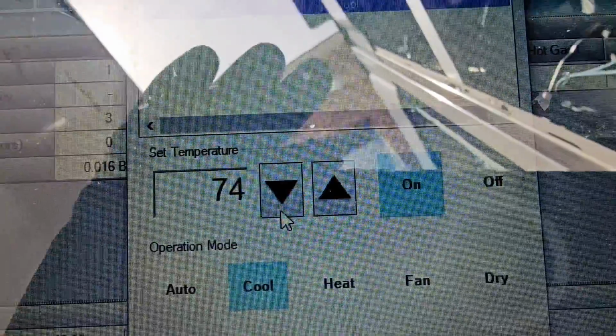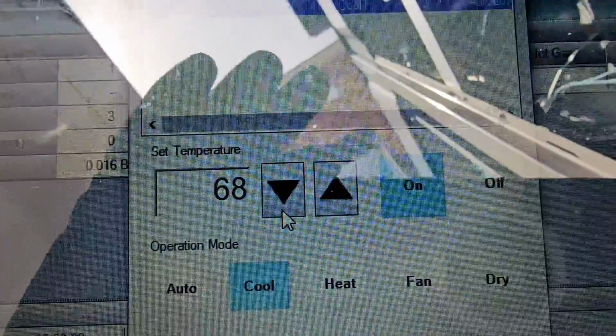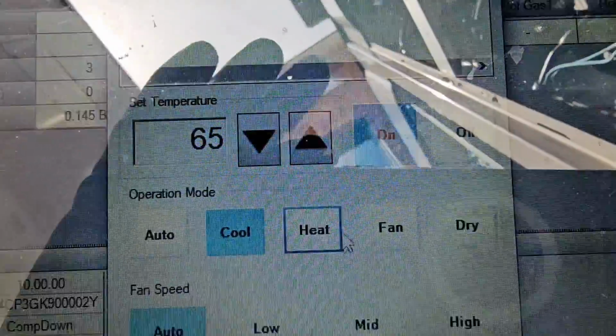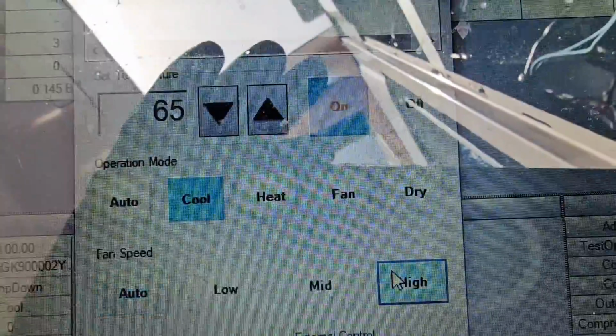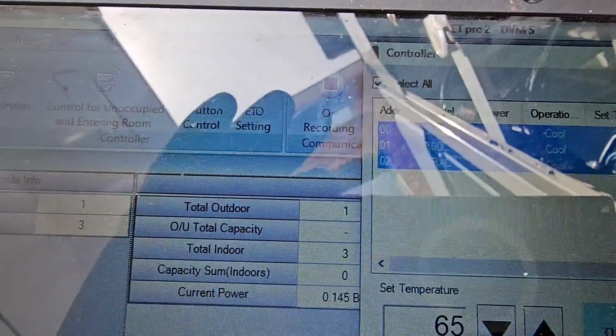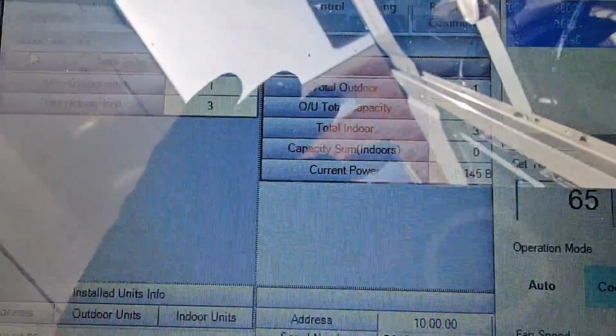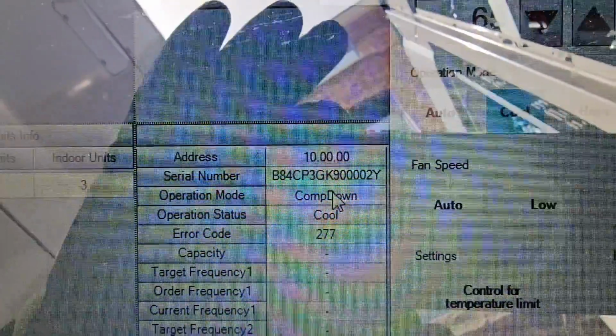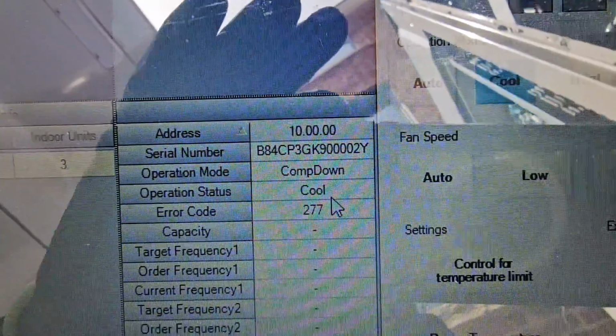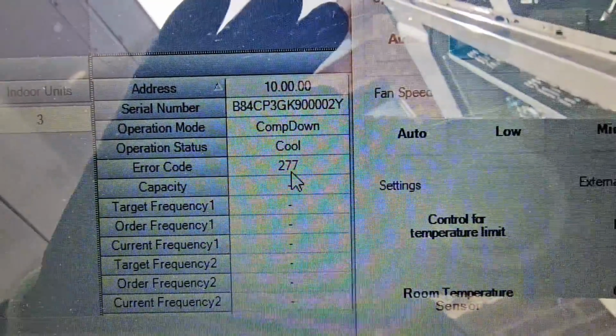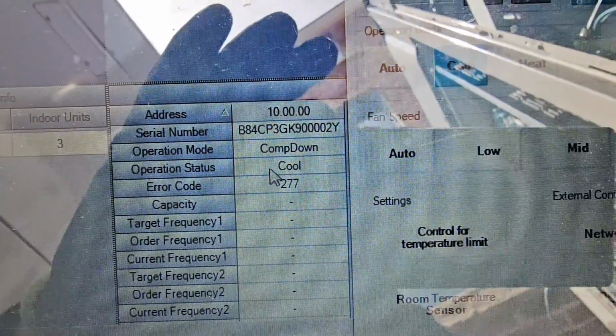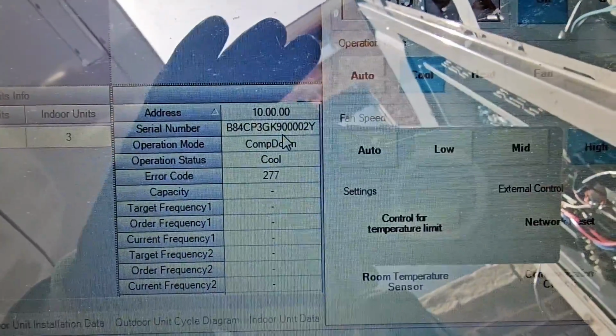Putting them on cooling, on, turn the temperature down to 65, fan speeds on high. All right. Total outdoor unit 1. Total indoor units 3. Operation modes, compressor down. Error 277. Okay, that means low pressure, I'm pretty sure.